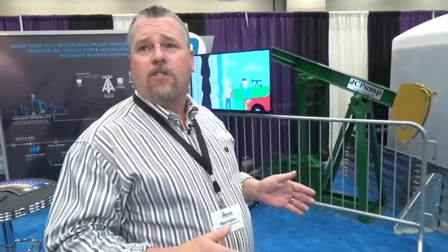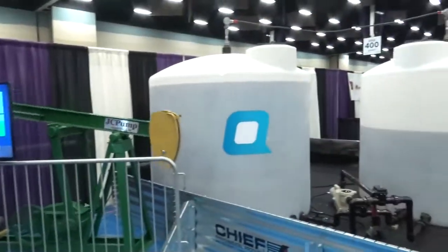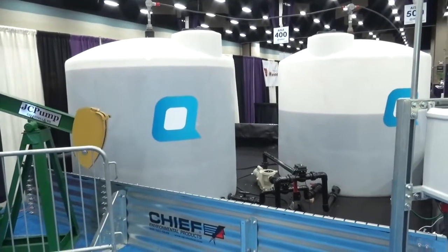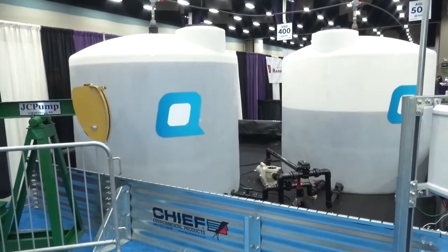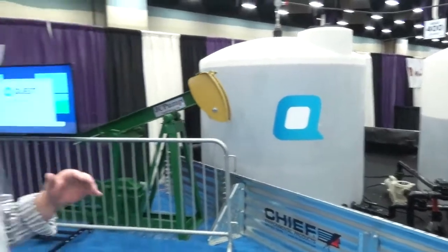With the injector well, if your injector well went out and your pump jacks, these little guys, kept on pumping the water, what would happen is it would overflow your tanks. So what we're able to do is stay in front of it. Let's just say you're producing a lot of water that day for whatever reason, and your pump jacks are putting in way too much. We can actually shut the pump jacks off for, say, 2 hours, let the injector pump catch up, and then kick the pump jacks back on, and that streamlines the performance of your oil production. So you're getting the maximum production out of that site without using timers, without best guess. It is scientific at that point.